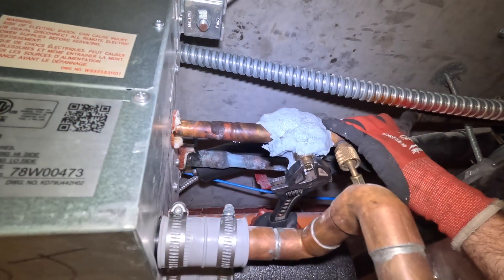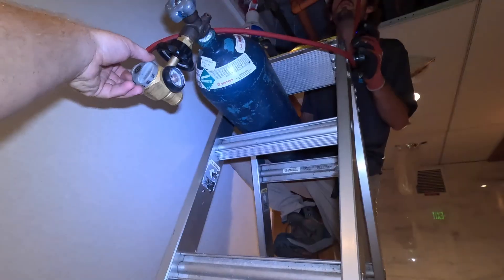We got to open these ball valves because we already know they're not holding. Yeah, it's leaking through there. The ball valves themselves aren't completely sealing right now — this popped up to 175. You can't even turn them. It's dropping — skip counting.